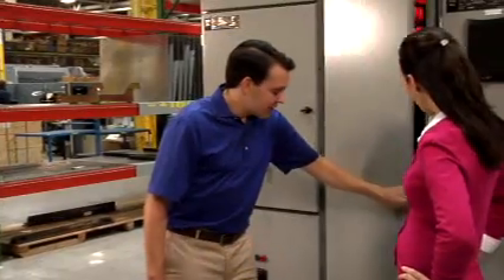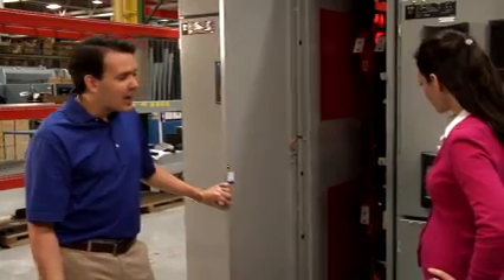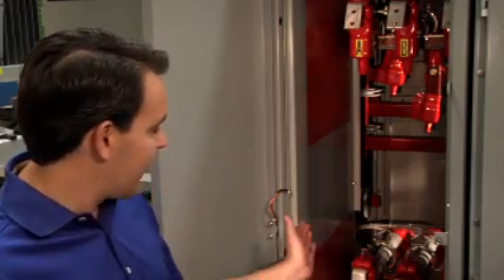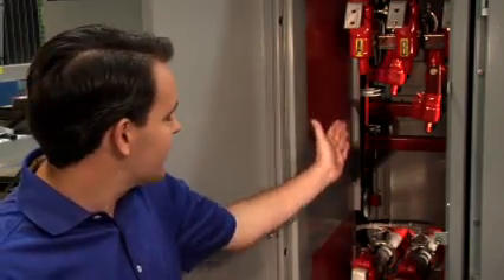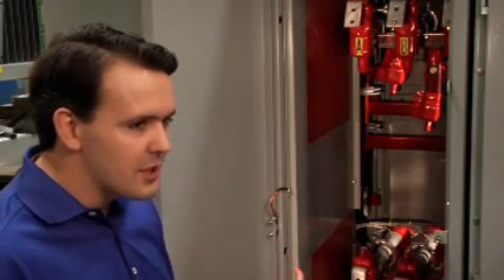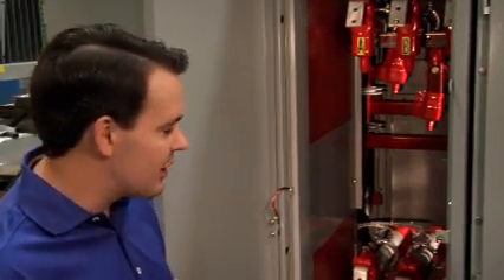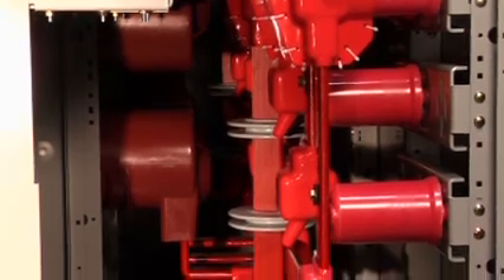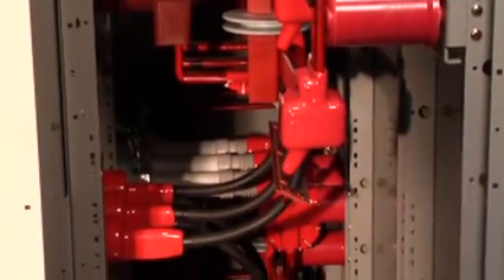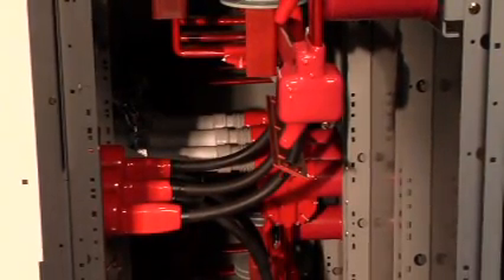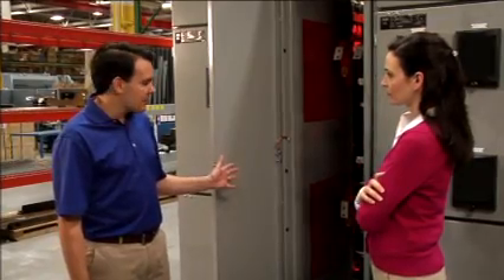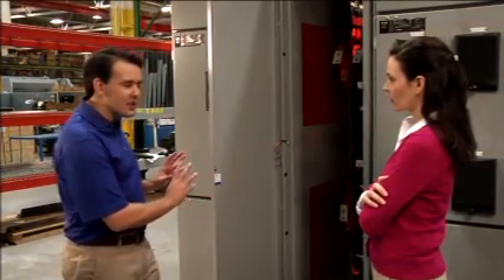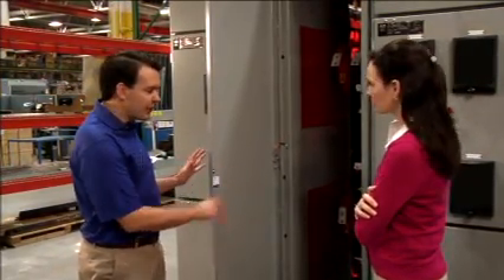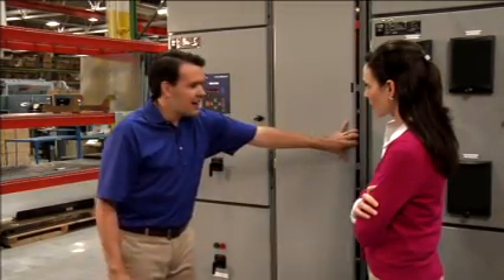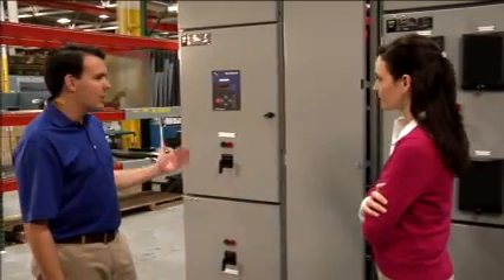Behind this compartment here, you can see access to all of the primary cable connections. If you look here, we've got the upper and the lower breaker cable connections. And this is unique to this particular type of medium voltage switchgear. Typically, this will be found behind the breakers in a 100+ inch deep switchgear section. So by making all this accessible from the front and making all of our connections that are behind the switchgear maintenance-free, we've now eliminated the need to access the side of the structure or the rear of the structure.